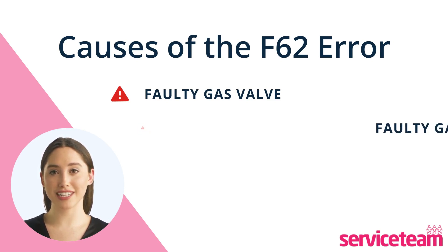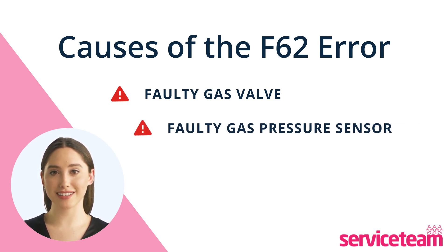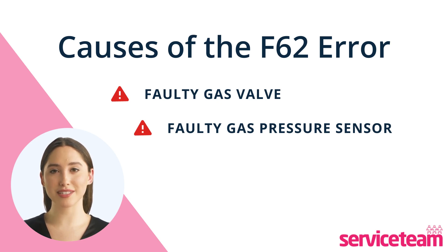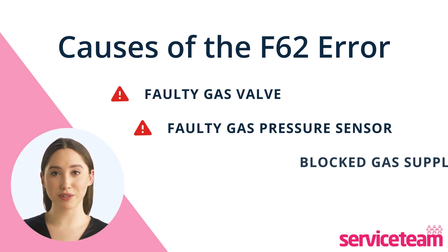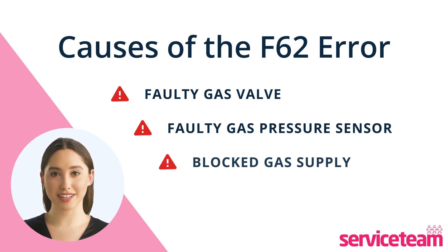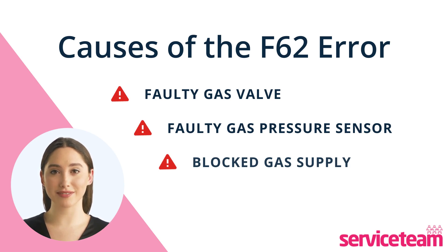Another cause could be a faulty gas pressure sensor. It acts as a safety monitor for gas pressure levels. If it malfunctions, it may send wrong signals to the boiler, causing it to shut down unexpectedly, resulting in heating or hot water supply issues. If the gas supply to your boiler is blocked or restricted due to debris in the gas line or a faulty gas meter, it can also trigger the Vaillant F62 error code.